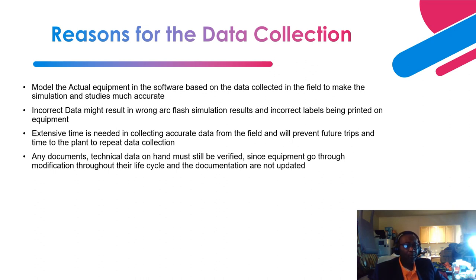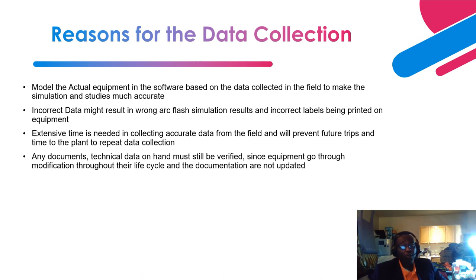You'll be amazed that sometimes when you go to the field, parameters on the equipment do not match what is on the drawing. This is a good time to update your drawings to reflect what is in the field. Also, any documents and technical data must be verified. Some plants have undergone modifications throughout their life cycles — for example, an additional section of medium voltage switchgear may have been added that hasn't been updated on the drawings. When you go to the field and the equipment is there, reflect what you've seen in the field on the drawings and get them updated.